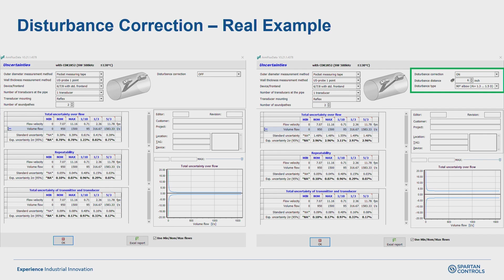I've sort of already covered this, so I don't want to spend too much time on it, but if we want to improve accuracy above that 1%, there's a couple different ways we can accomplish that. We can add more transducers, which sounds like an over-the-top solution. But if you have pipe disturbances you just can't get around, and disturbance correction isn't an option for whatever reason, we can add more transducers to the system. Obviously that's going to add cost, so just be mindful of that, but know there is another option there.